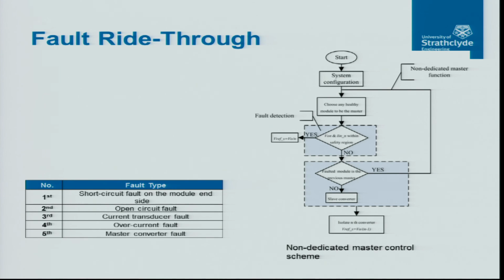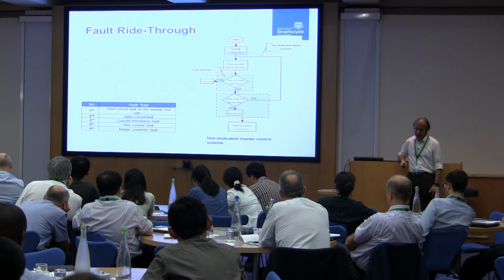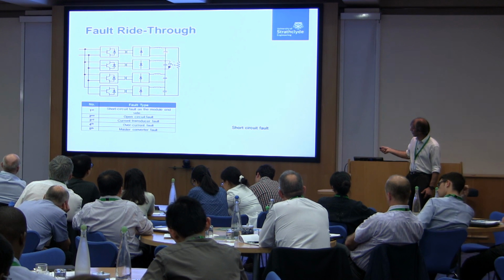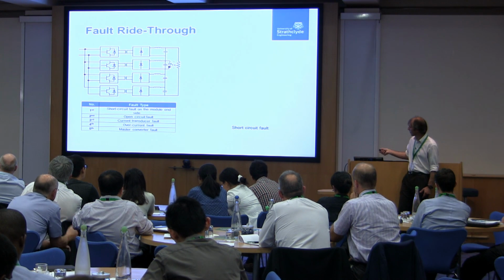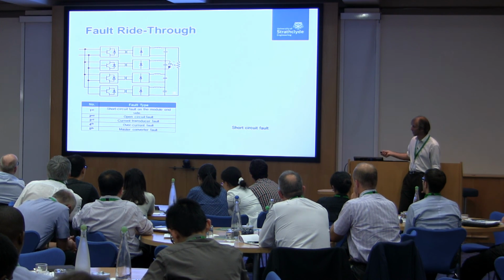So we're looking here at a control system which is monitoring for any devices which are out of tolerance, taken as a 10% variation, and then detects if the master is wrong and reallocates the master, and then rebalances all the voltages across the cells. The idea, going back, is that you've added redundancy. So under normal operating conditions, these capacitors are operating at a balanced voltage which is less than what could be withstood by the device ratings. In the event of a fault, we can take out one device and all these devices here increase to compensate for the loss of the voltage here. Provided you've got enough cells across there, the number of additional devices that you need in order to implement that redundancy should be relatively small. Very similar idea to that taken up with the MMC circuits.